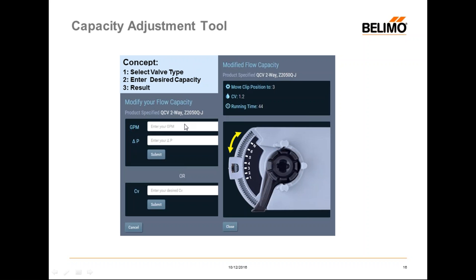Should you not know the GPM — maybe it's a retrofit situation and you want to replace like-for-like CV — you can type in the CV value directly. Hit submit and it will tell you to move the clip position from N to the appropriate position. This procedure can also be done for the PI-QCV. With the PI-QCV, you don't need to know the delta P — just plug in the GPM you need and hit submit to get your new clip setting.